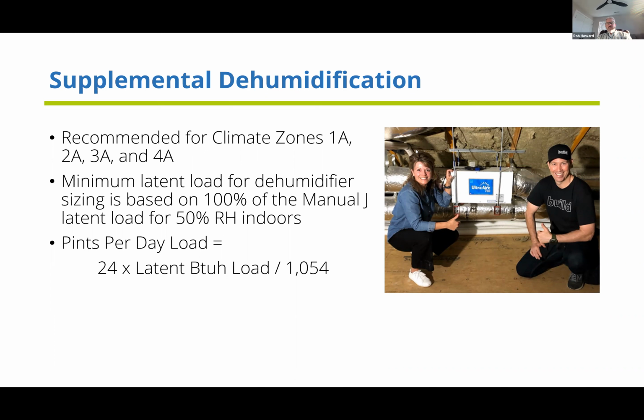Supplemental dehumidification is recommended in LLH for climate zones 1 through 4, and that's North Carolina - that's where I live. We're primarily climate zone 3 and 4, with just a little bit of climate zone 5 up in the high country where App State is located in Boone. So most of the state, and really most of the Southeast, needs supplemental dehumidification in these low load homes.